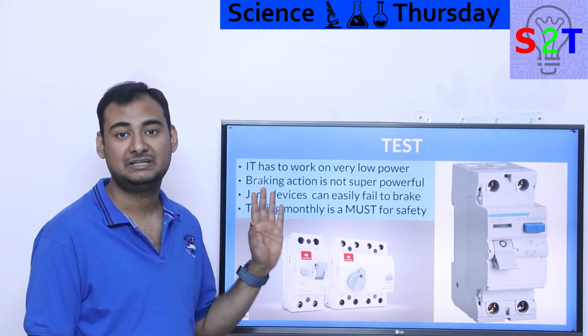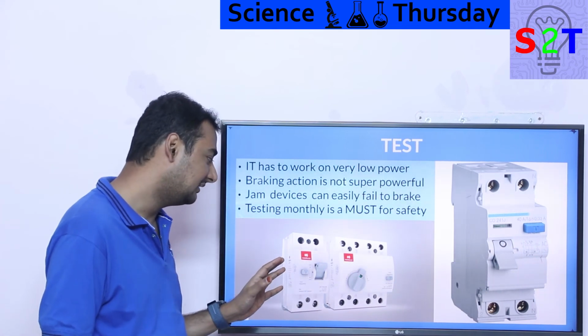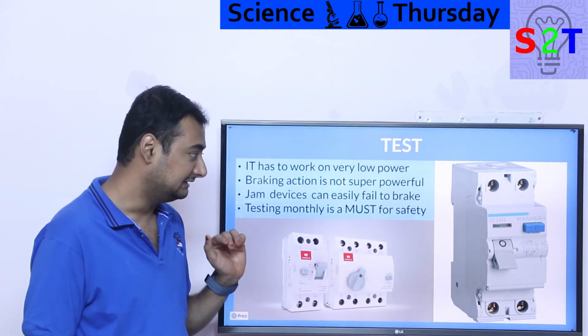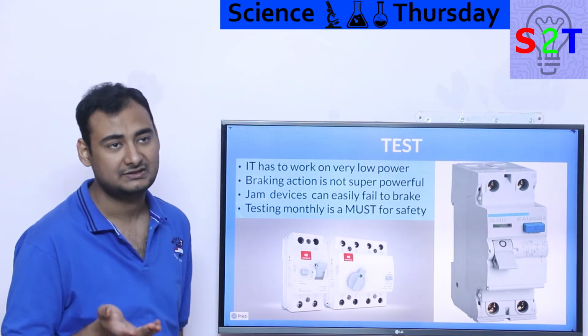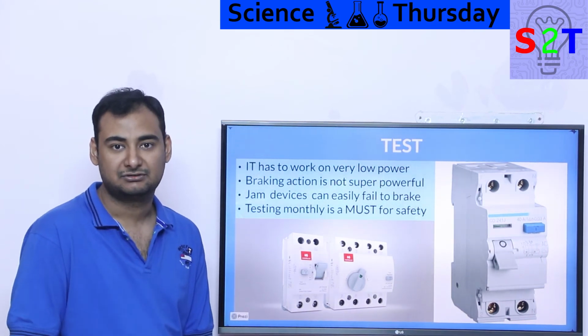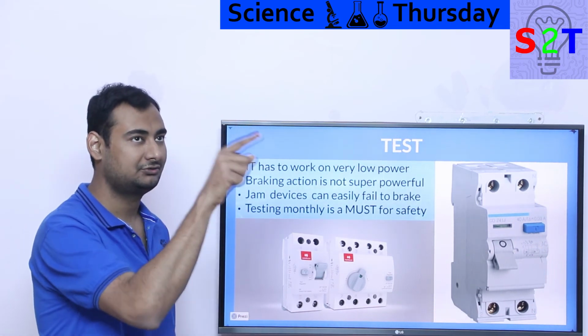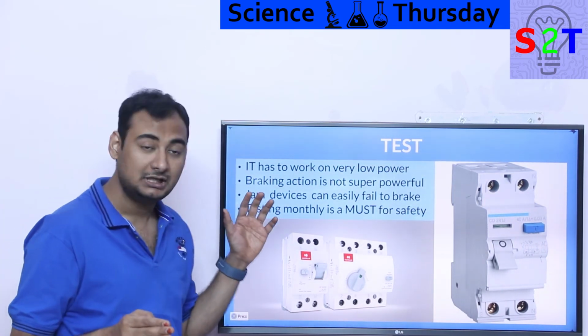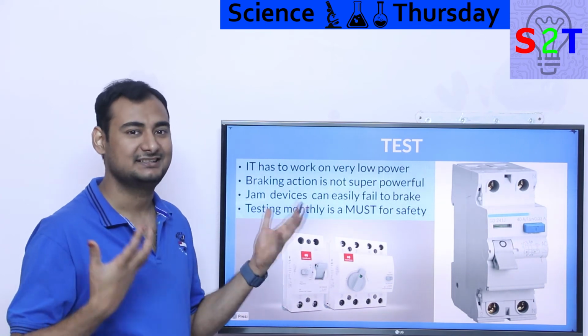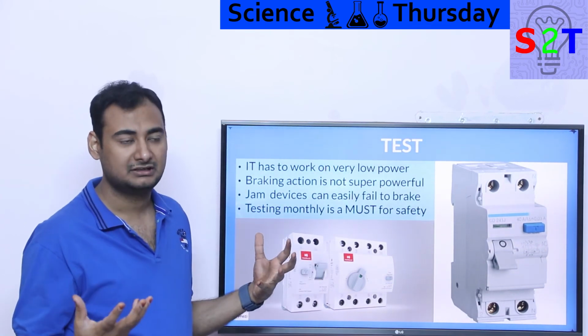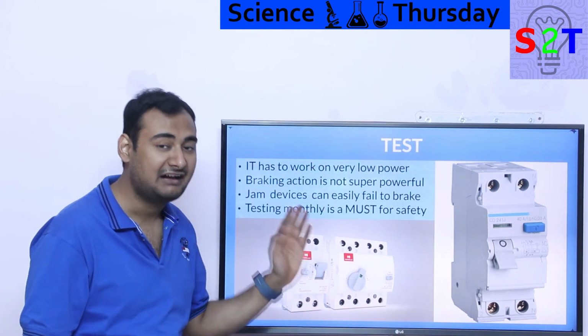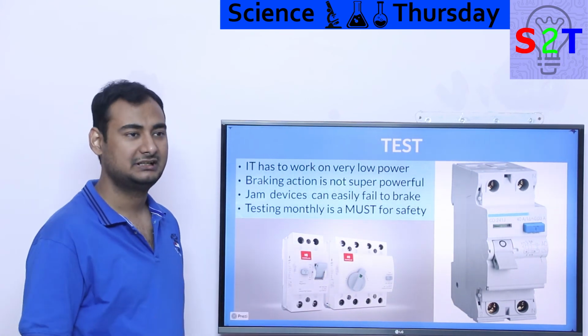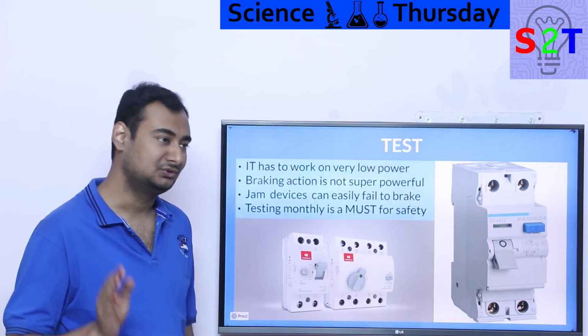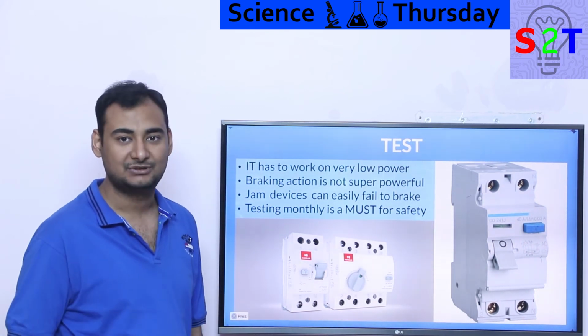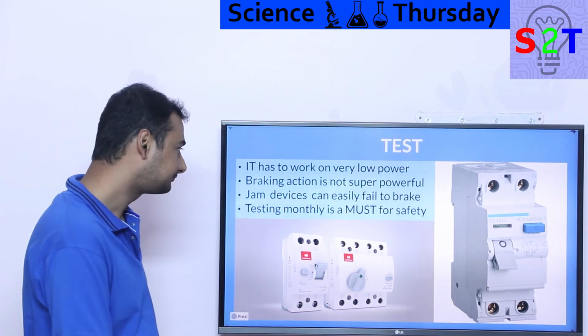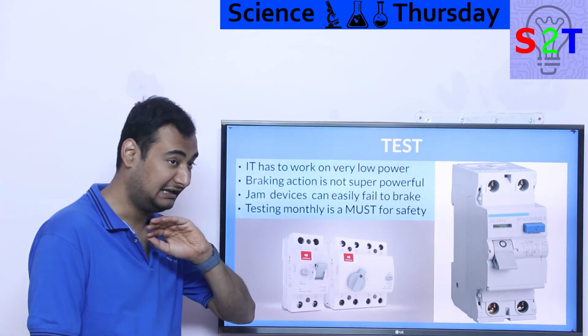Now you're supposed to trigger this puppy every month. Every device will say test monthly, test regularly. Most of the time it's generally test monthly. So you're supposed to test, have one day, on every 31st or on every first, just go everywhere, tuk, keep doing this. You have to do that because of the fragile nature of these things. Actually it's not fragile, it just does not have enough oomph. Normal wear and dust and grime can jam this puppy. You have to test this thing. Do not just put it there, at least test once a month and you will be safe. You do not want to be in a position where the GFCI did not trigger because you did not test it in the last 5 years. So that's why the test button is so important, and that's why everywhere you will find this button.